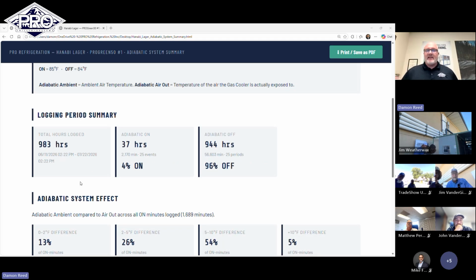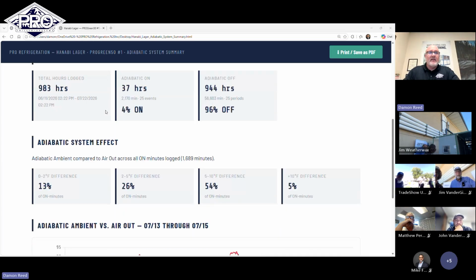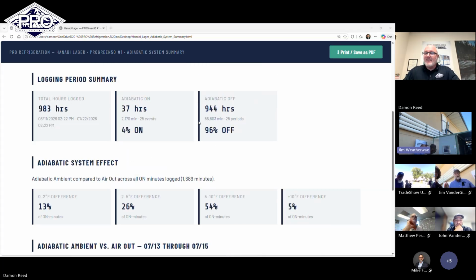I went ahead and pulled the same data set. We grabbed 983 hours, and the adiabatic was on for 37 hours, or 4% of the time. It was off 944 hours, 96% of the time, in that period. Those were all operating hours, the total operating hours of the chiller. This is from June 11th to July 22nd. This is the time period where the adiabatic solenoid was engaged, or that output was calling for it: 4%, 37 of those hours.